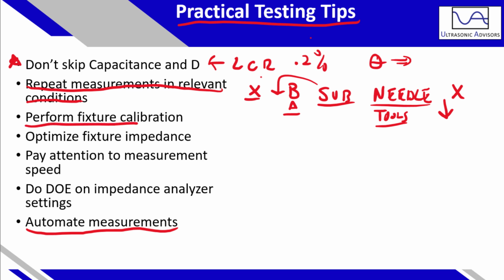The next is to perform fixture calibration. That's also just to understand what the impedance of your fixture is to begin with. You don't want a fixture with a series resistance of 100 ohms. You don't want a fixture with 5 nanofarads or 3 nanofarads of parallel capacitance. So you should actually measure your fixture just to understand where you lie. If you need to, optimize it, because you don't want to calibrate to very large extents if you can avoid it. But nonetheless, using fixture calibration will lead to better results.